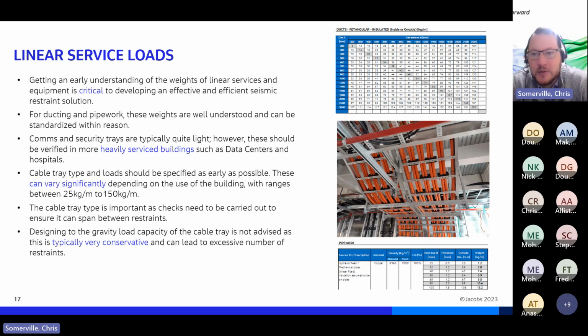The main challenge we tend to find is in the cable trays for the electrical. These can vary significantly - I've had projects where 175 kgs a meter is what we've been specified, with 5 of them. That's almost a ton in some projects, a meter of electrical cables, which is significant to try and restrain, especially if you've got a lightweight roof to hang it from. It can become a very challenge.